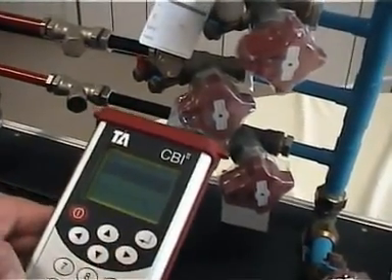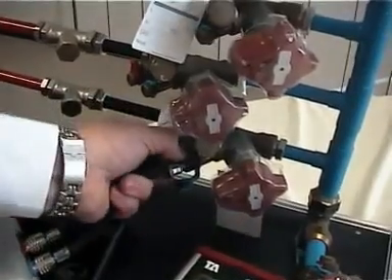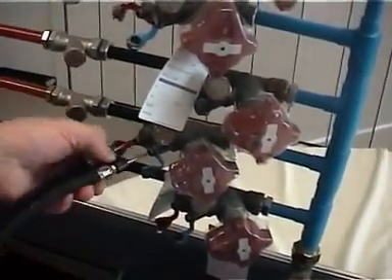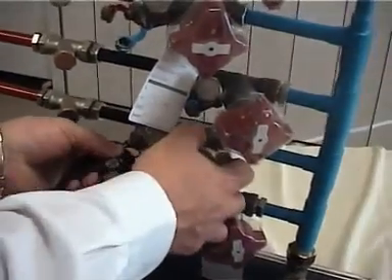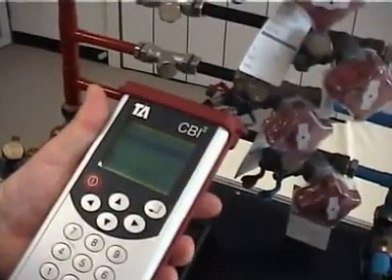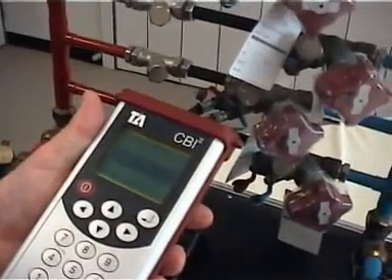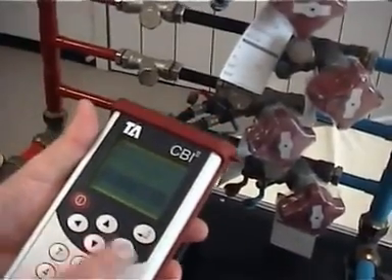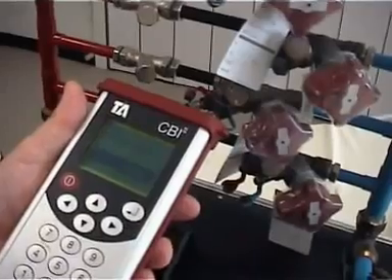We chose one. Now we're going to measure valve number two. Remove it from the points, and move on to your next valve. Dust covers are removed. The process is to put the measuring points into the valve stem, and continue on as before. Check the information is correct. It tells us our design flow, which was 0.06 liters. Press enter. The number of turns on this one on valve two is once again two turns.